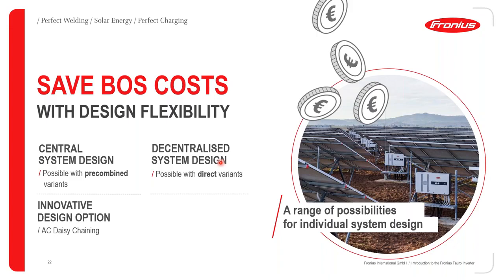And this basically allows you to make a lot of savings on your AC cabling that you'd normally use for inverters that do not support AC Daisy Chaining. Also, in terms of the flexible connection as far as cabling is concerned, with the Tauro inverter, you can go in with anywhere from 35 millimeter square cross section up to about 240 millimeter square on the AC side. And that of course would also depend on the distances that are involved from the inverter to the transformer or the point of interaction, and also the amount of power that you want to transport through that particular cable.